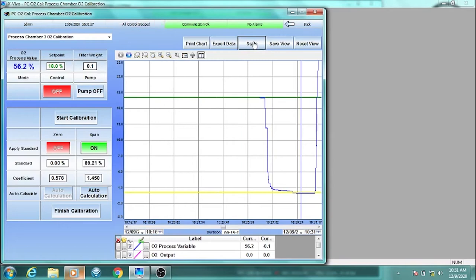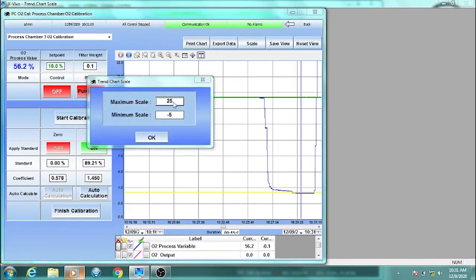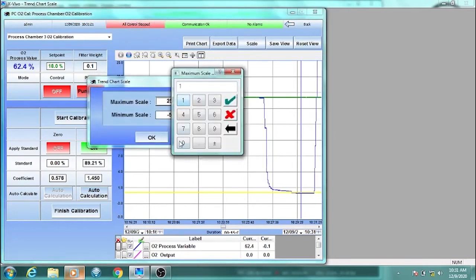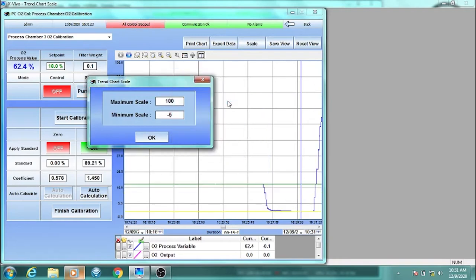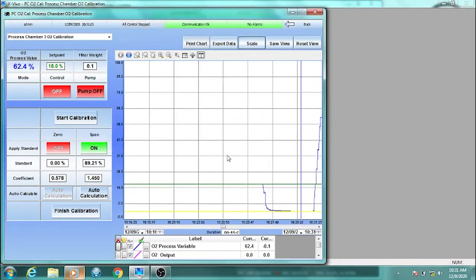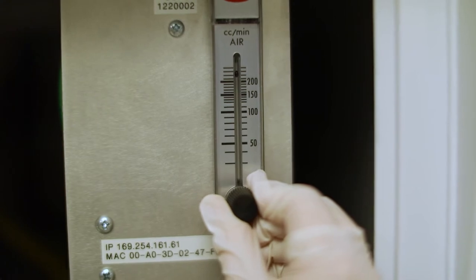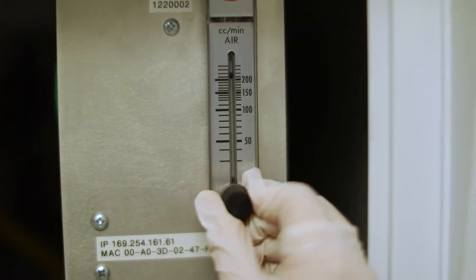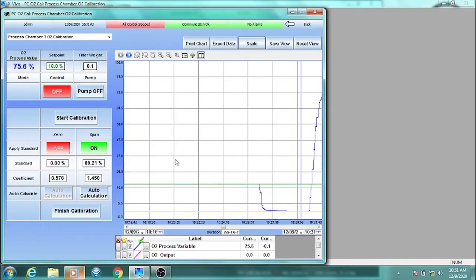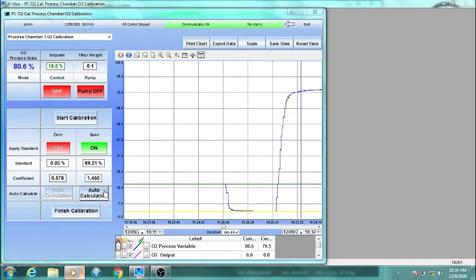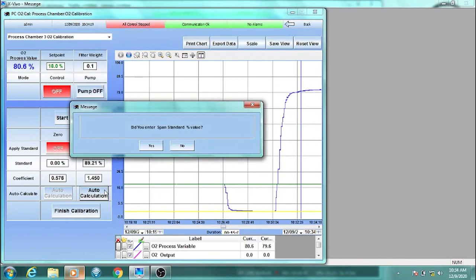Change the scale to a higher value to watch the oxygen reading increase as the span gas runs across the sensor. Check the flow meter again to make sure it is still around 200 cc per minute. It will take a few minutes for the reading to level out. Once it levels out, click the Auto Calculation button if the value is not within plus or minus 0.1 of the span standard, in this case 89.21%.